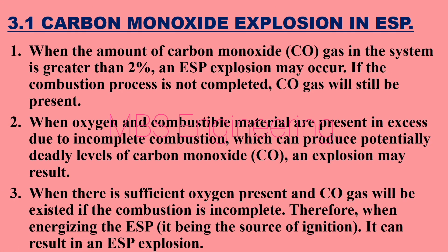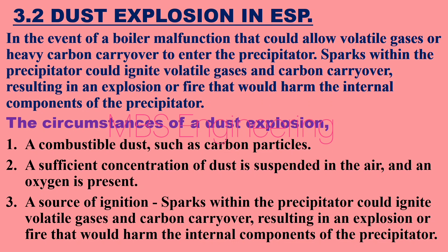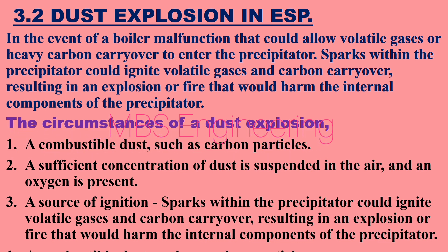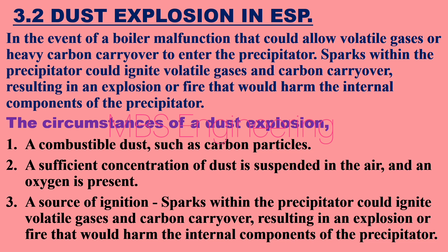Next, we will look at dust explosions or fire in the ESP. Point 1: In the event of a boiler malfunction that could allow volatile gases or heavy carbon carryover to enter the precipitator, sparks within the precipitator could ignite those gases and carbon carryover, resulting in an explosion or fire that would harm the internal components. The circumstances of a dust explosion require: a combustible dust such as carbon particles, a sufficient concentration of dust suspended in air with oxygen present, and a source of ignition.